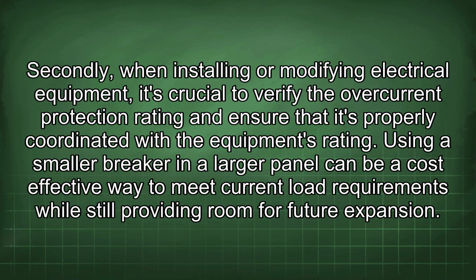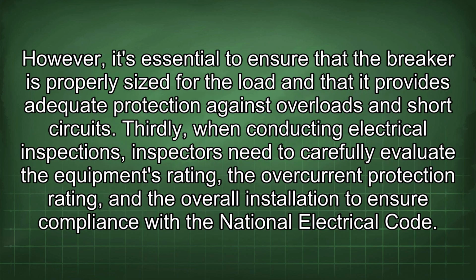Secondly, when installing or modifying electrical equipment, it's crucial to verify the overcurrent protection rating and ensure that it's properly coordinated with the equipment's rating. Using a smaller breaker in a larger panel can be a cost-effective way to meet current load requirements while still providing room for future expansion. However, it's essential to ensure that the breaker is properly sized for the load and that it provides adequate protection against overloads and short circuits.